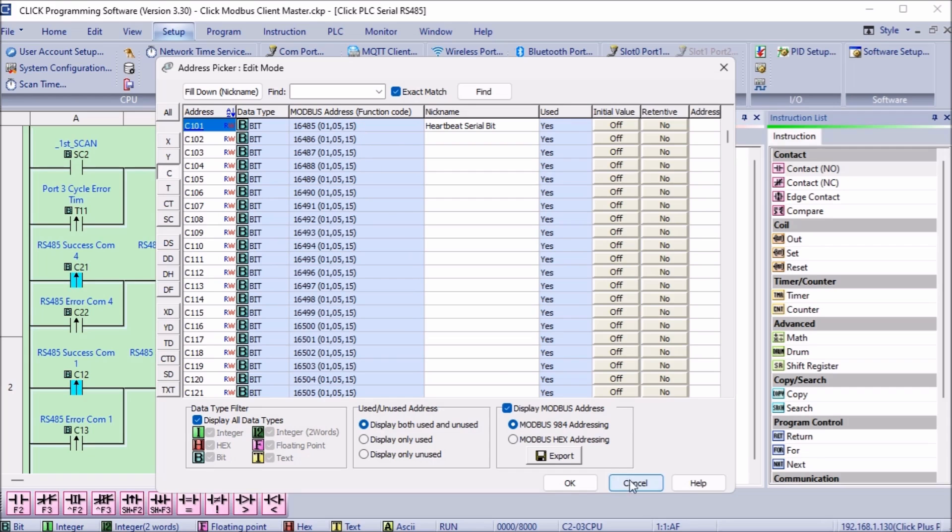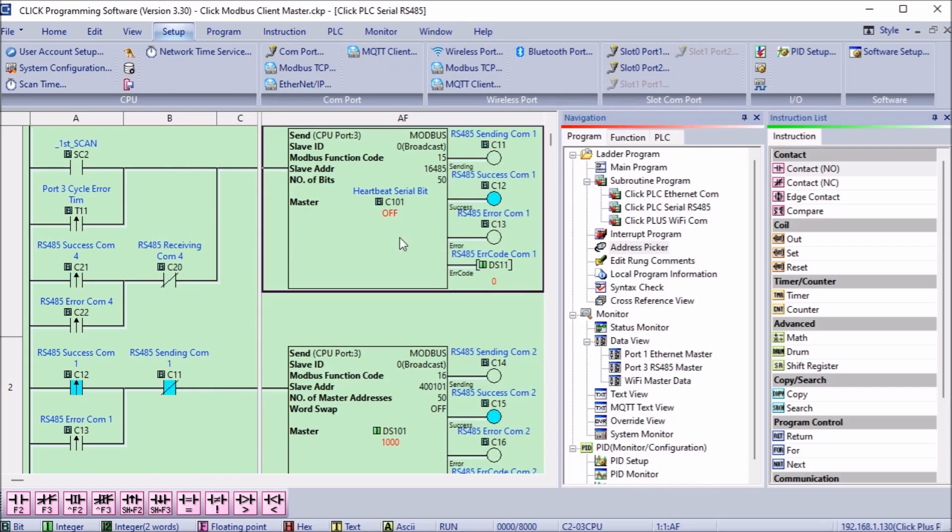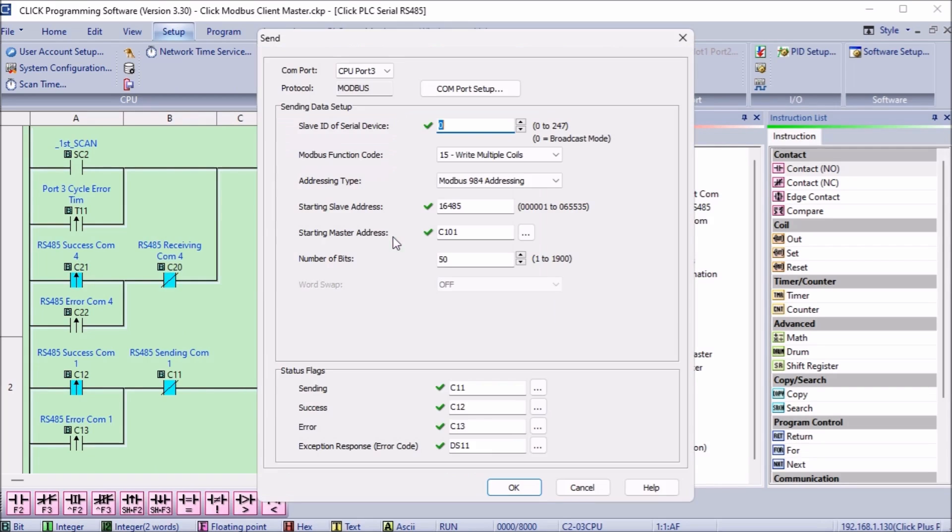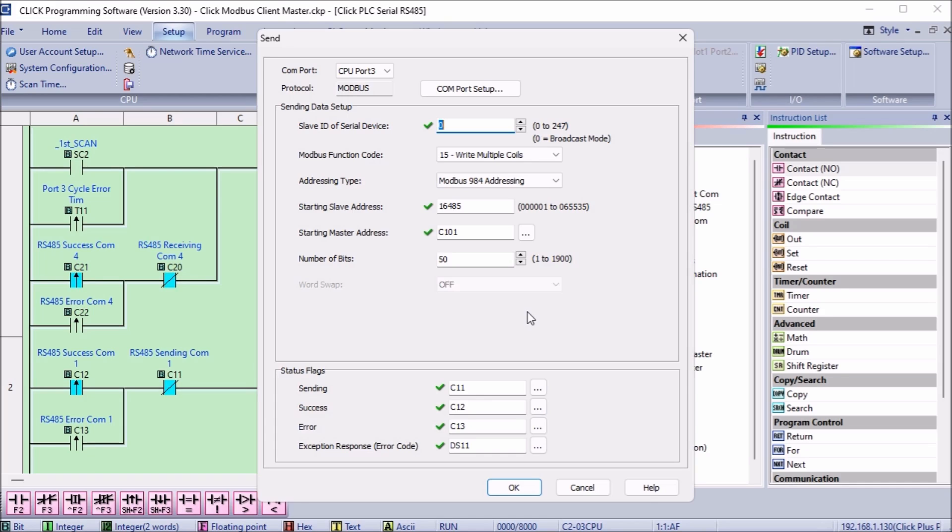Looking back at the send instruction, we are also sending 50 bits. This means that bits C101 to C150 from the master PLC are being sent to bits C101 to C150 of the slave PLC. Status flags are then set for the send instruction.